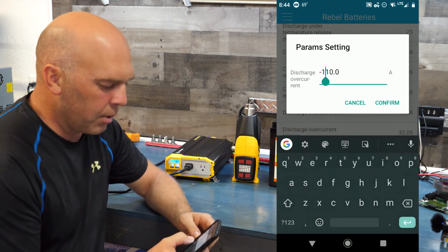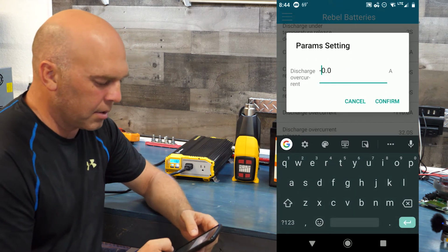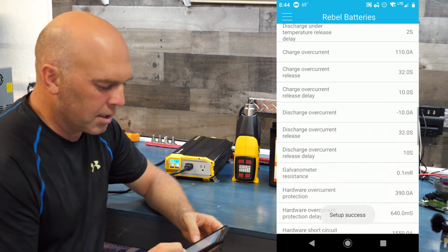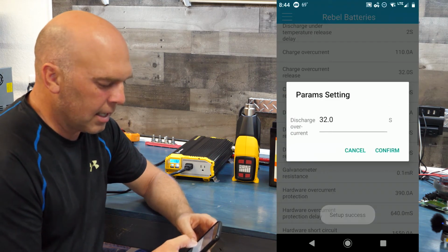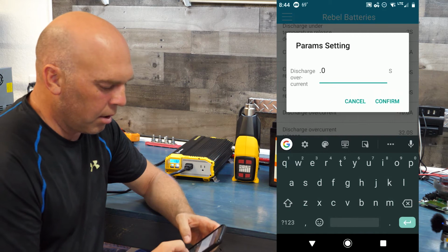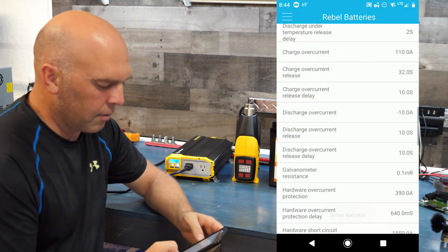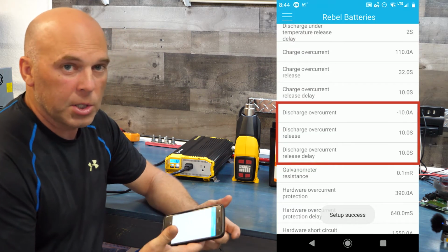Watch this. We'll go down to discharge over current, and we can change this to say 10 amps, minus 10. So if it draws 10 amps for greater than 10 seconds, we will turn it off for 10 seconds. Confirm. That's it. That's all you got to do to change those settings around.